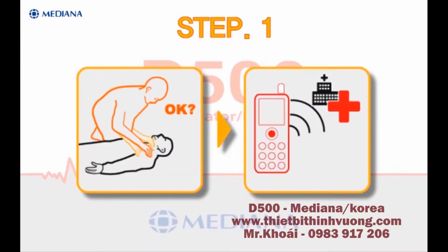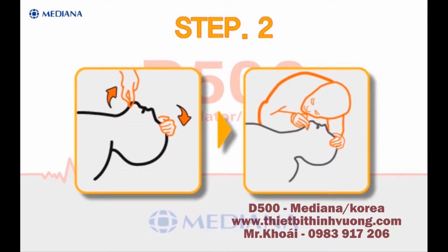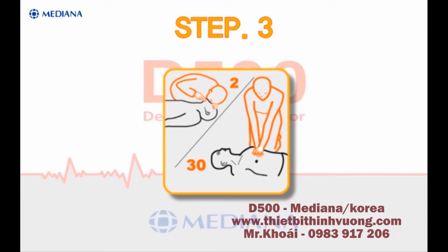Are you all right? Call for help. If pads are connected to defibrillator monitor during step 1, defibrillator monitor will go on to step 4 directly. Open the airway. Check breathing. If pads are connected to defibrillator monitor during step 2, defibrillator monitor will go on to step 4 directly. Begin CPR. Give 2 breaths. Stop CPR. If pads are connected to defibrillator monitor during step 3, defibrillator monitor will go on to step 4 directly.